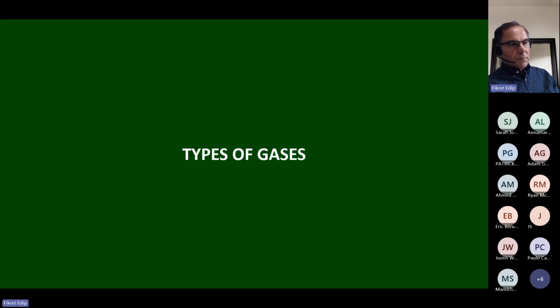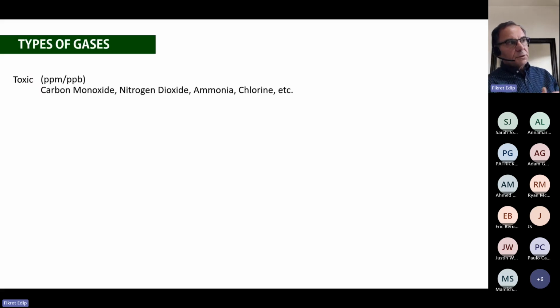But what are we looking for? What type of gases are we looking for? That goes into certain categories. First, we look at the toxic gases. Toxic gases are typically measured in parts per million or parts per billion. These gases, for example, are carbon monoxide, the silent killer, we all know about it. Nitrogen dioxide, believe it or not, is much more toxic than carbon monoxide. I'll give you an example. The low alarm set point for carbon monoxide is 25 ppm. For nitrogen dioxide it is 0.7 ppm, 0.7. It is a deadly gas.